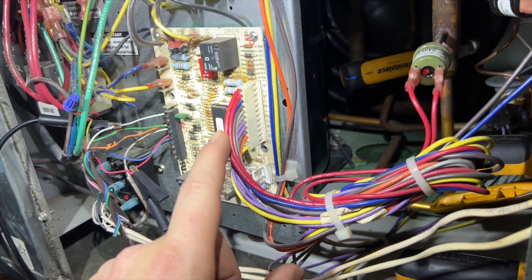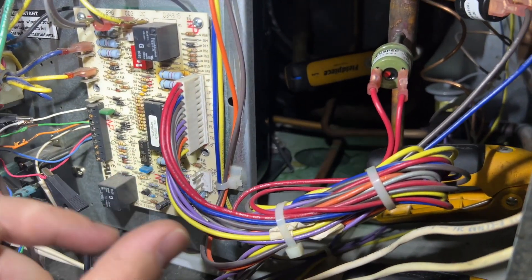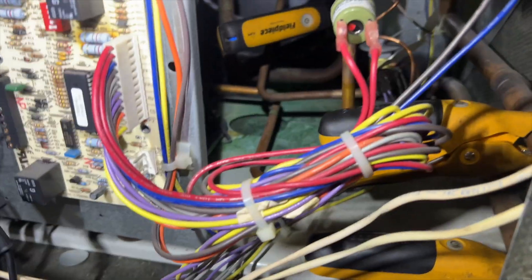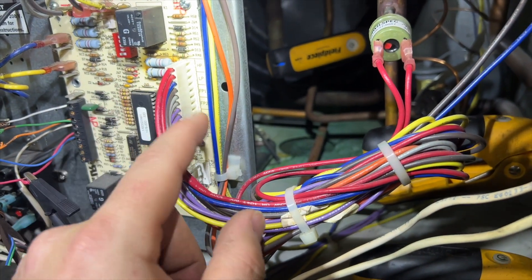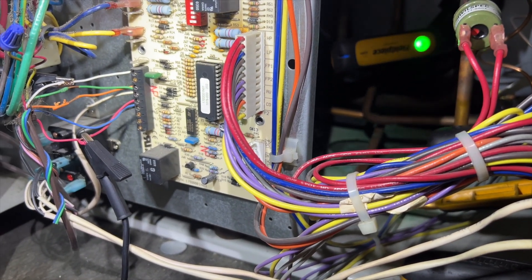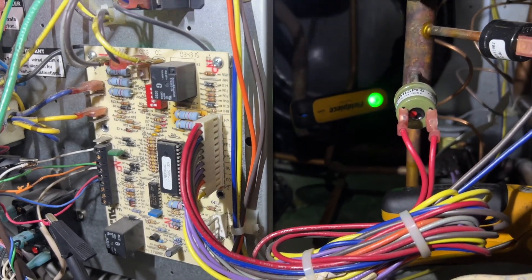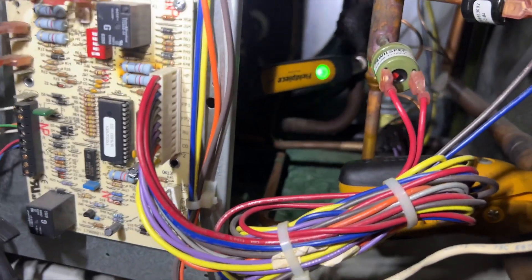FP1 and FP2 are thermistors — they're not a normally open or normally closed switch type. They're detecting temperature, and I think this is what's tripping it. So anyway, we'll go ahead and see if we can find any signs of refrigerant leaks so we can fix it. If not, I think we're going to charge it up just to get by for now.